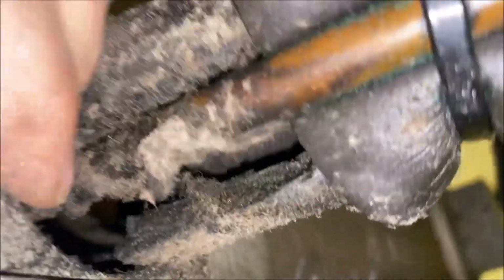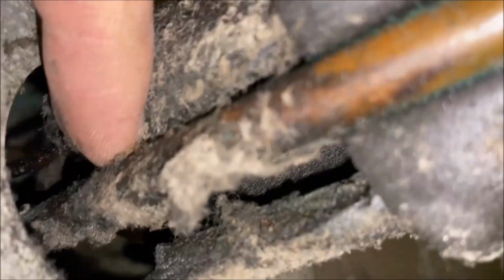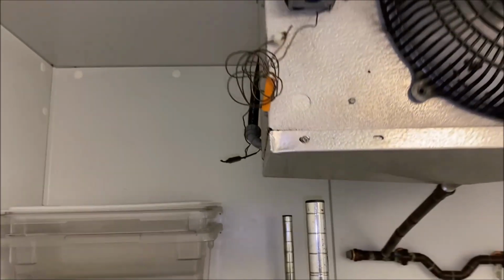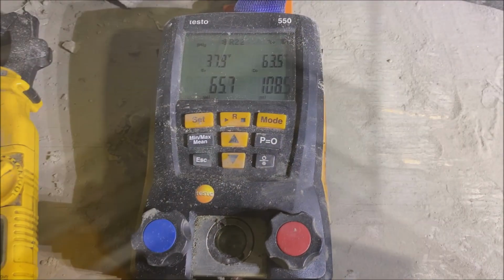Okay, next thing we want to do is check our liquid line solenoid. Now we're just going to peek in here. And as you saw, the thermostat was on the front of the box, but our solenoid is not here, on the liquid line or at the condensing unit. So my unit is short cycling.